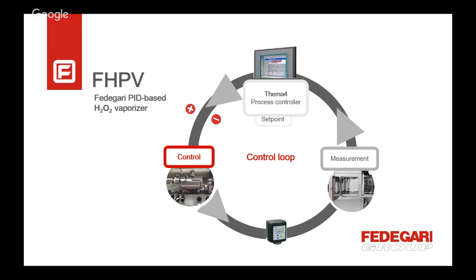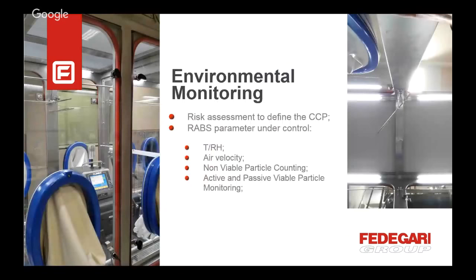The advantage of this technology is also that we have no issues with the variation of the plastic products that we are introducing into the material airlock, for instance. Plastic films are not the same. So if one plastic film is more absorptive than another, the system self-adjusts and you do not have to revalidate the whole process, because it keeps the concentration inside the chamber stable.